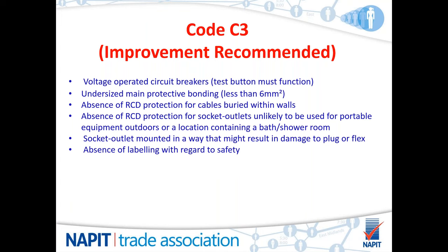So again, C3. Absence of RCD protection for cables buried within walls, C3, unless you can see damage to switch drops or the area surrounding switch drops. If it's in a place where people have put drawing pins near the switch drop, somebody's going to drill holes for a shelf unit close to the switch drop, they don't realise how close they are, and that could determine whether it's a C2. But if you can't see any problems, C3.